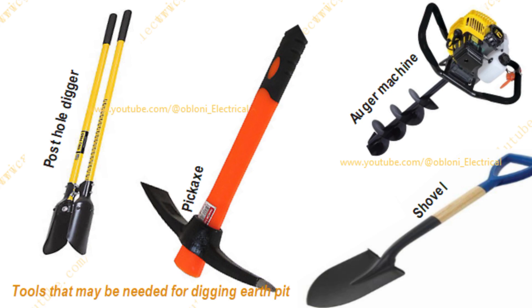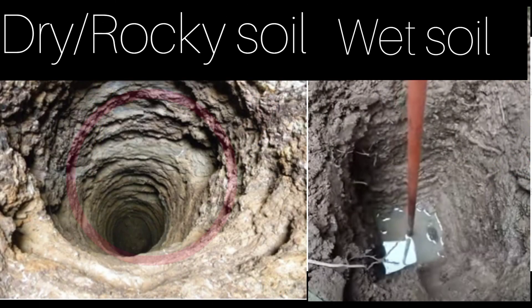Coming back to the question of how deep should we dig and how long should the rod be — the length of your rod will depend on a lot of factors. For example, if you have to bury your earth rod in a rocky area or rocky soil, you may have to dig deeper. In areas where the water table is very high, or closer to the earth's surface, you may not need a longer rod. In fact, there are places where even in the dry season the water table is as high as three feet down from the surface. In such areas, a copper rod of just four feet long will be fine, and you can drive the rod directly into the ground without necessarily digging.